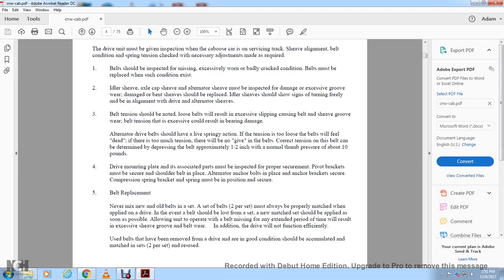The anchor bracket secured with the compression spring bracket and spring must be in position and secure. Five, belt replacement. Never mix new and old belts in a set. A set of belts, two per set, must always be properly matched when applied to the drive.